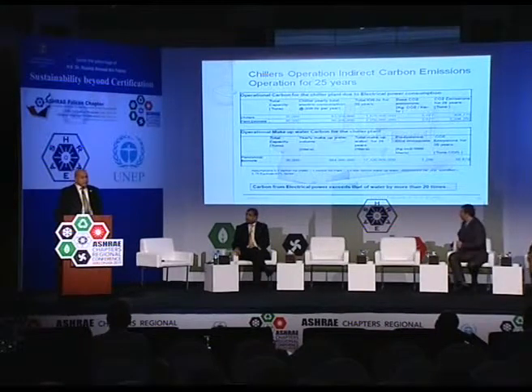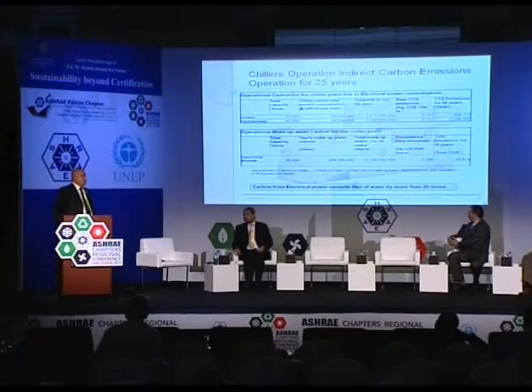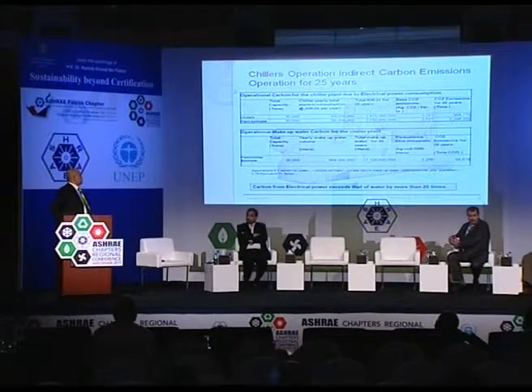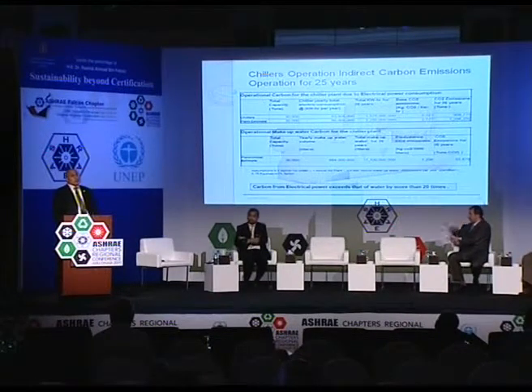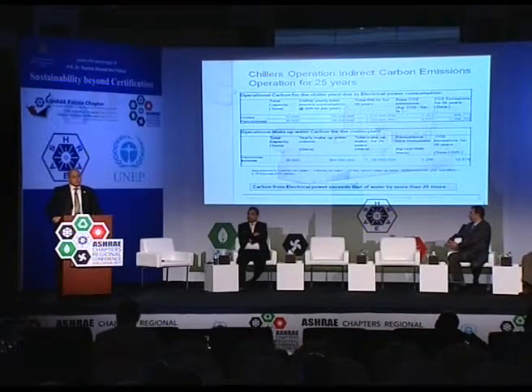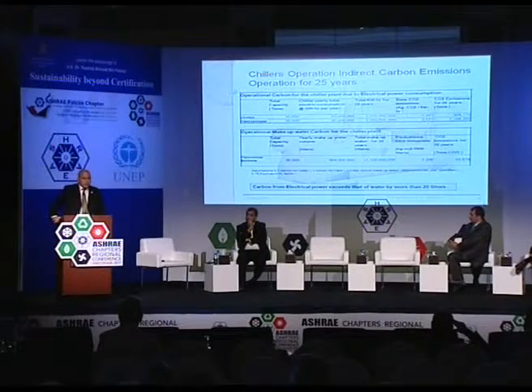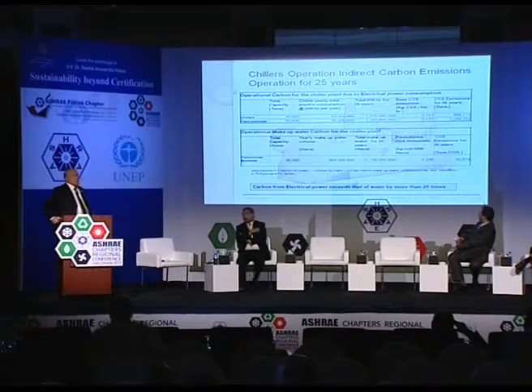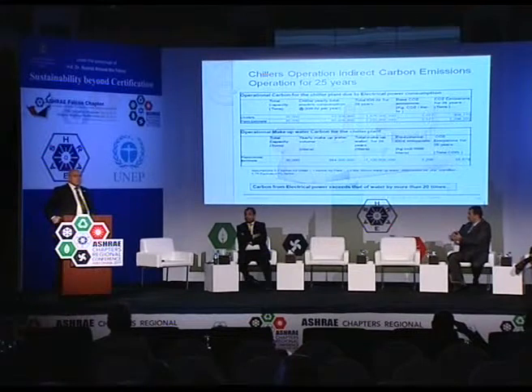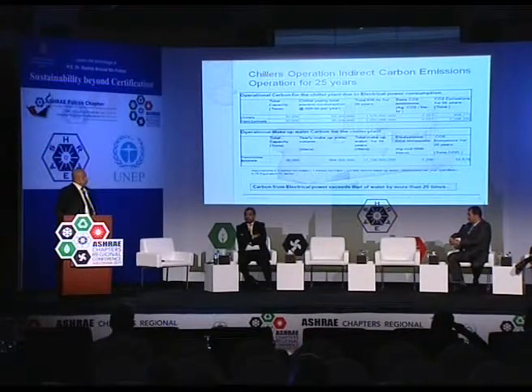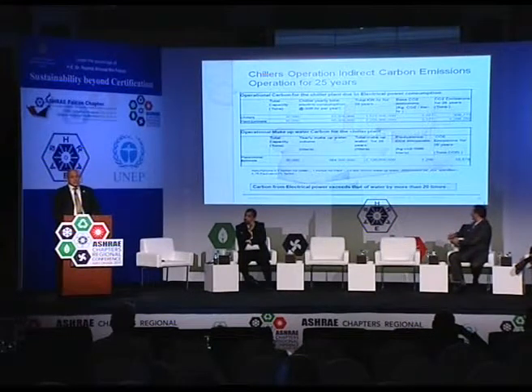Now we look at another important aspect. This is the chiller operation indirect emissions, which means this is electricity. We have 30,000 tons, and the yearly total electric consumption in kilowatt hour is around 63 million kilowatt hour per year. For 25 years, you have 1.6 billion kilowatt hour. At the base CO2 emission of 0.577, this is based on combined cycle turbines used in Abu Dhabi, you will have around 900,000 tons of CO2. We do the plant estimate using the same criteria. It's around 1 kilowatt per ton. You will have a total of 1.3 million tons of CO2 for 25 years.